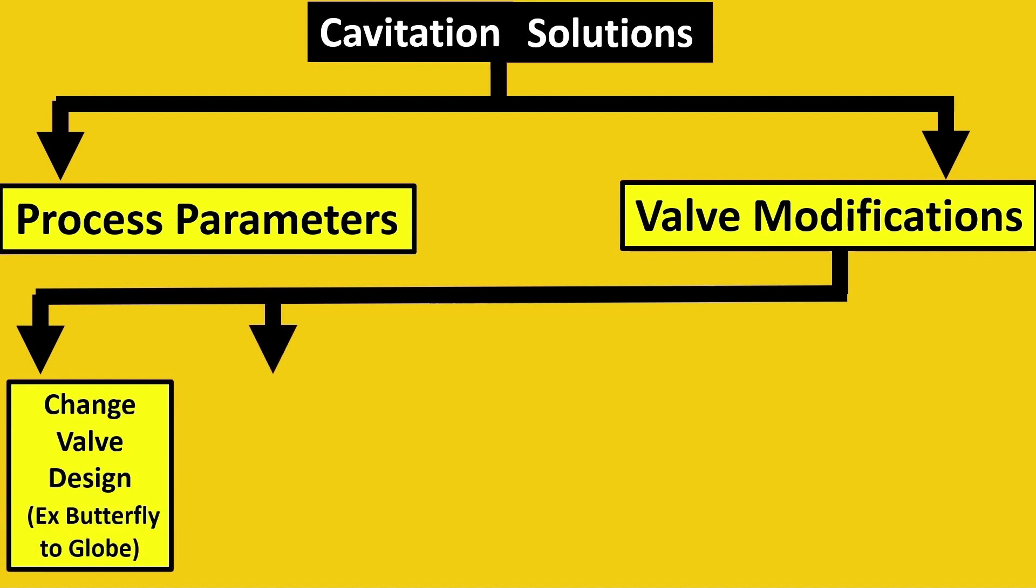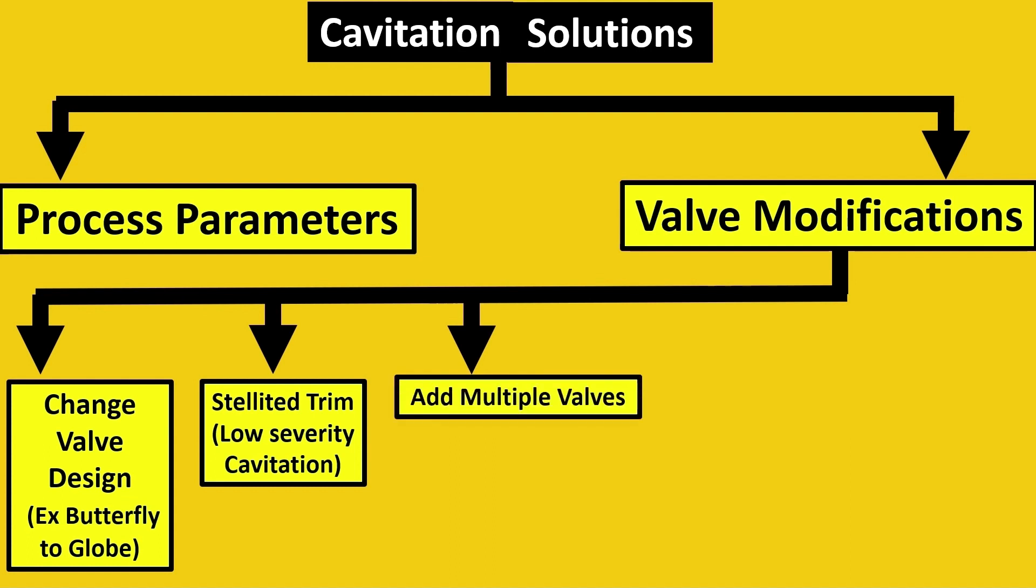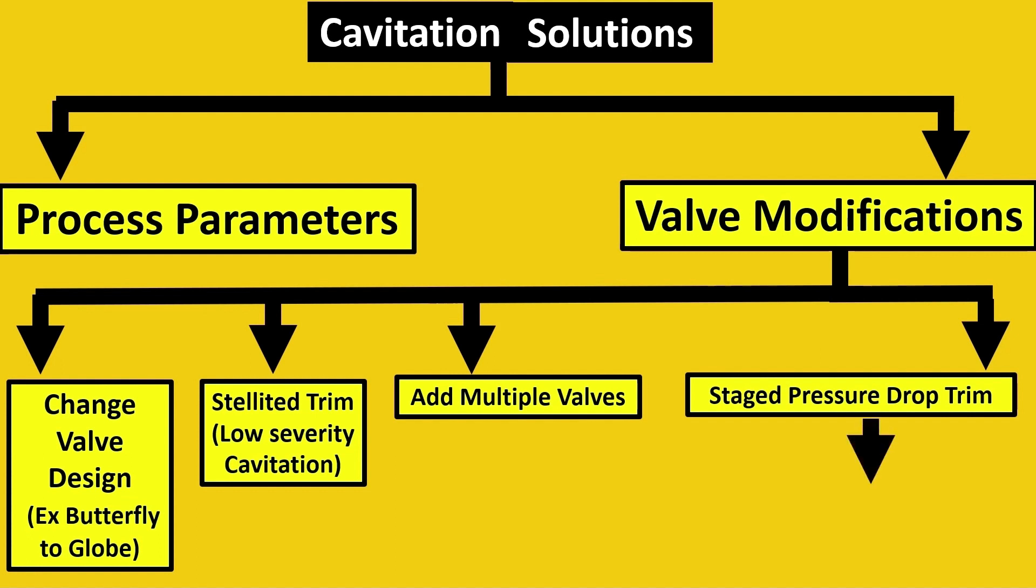The second thing is stellited trim, because stellited trim is basically where you just harden the trim material if the cavitation is not that severe, so it can sustain the damage of cavitation for a long period of time. If that's not working, then you go for multiple valves. But if multiple valves is an issue with you, you can go for stage pressure drop trim, which can further be divided into single stage and multi-stage trim.